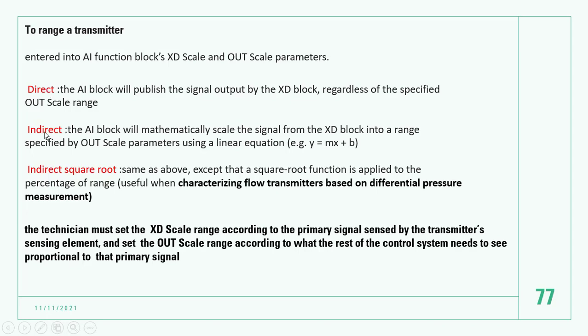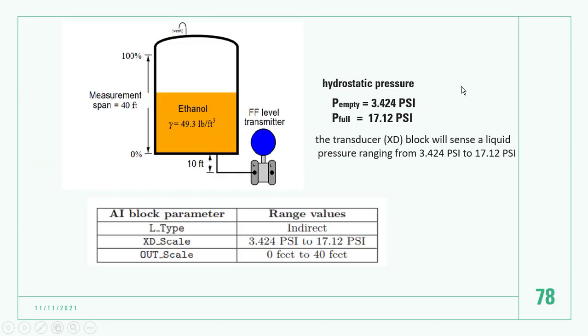This is indirect. The AI block will mathematically scale the signal from the XD block into a range specified by the out scale parameter using a linear equation. The indirect square root, this one is just for a flow transmitter, differential pressure flow transmitter, use the indirect square root. Okay, we should set up all of this. Okay, this is the example.